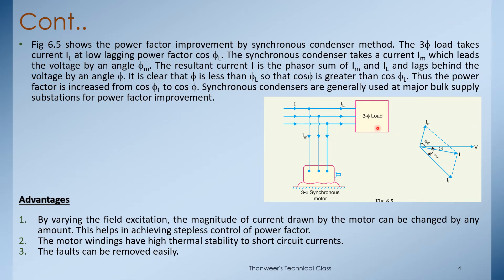This figure shows the synchronous condenser method. The synchronous current leads the voltage by an angle phi. The vector sum gives the resultant current, and the final phase angle is reduced. The power factor is thus improved. By varying the field excitation, it varies the magnitude of the current, providing stepless control of the power factor.